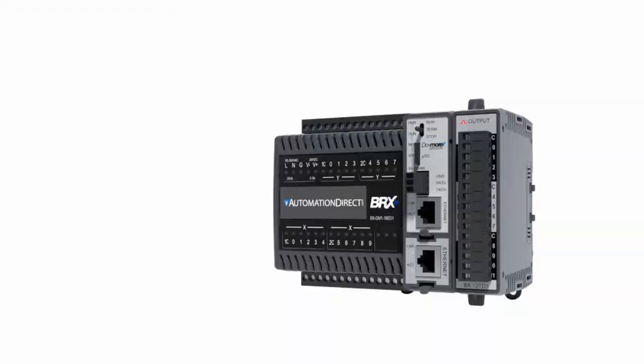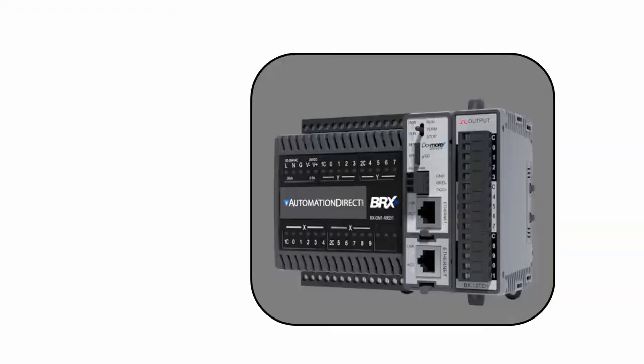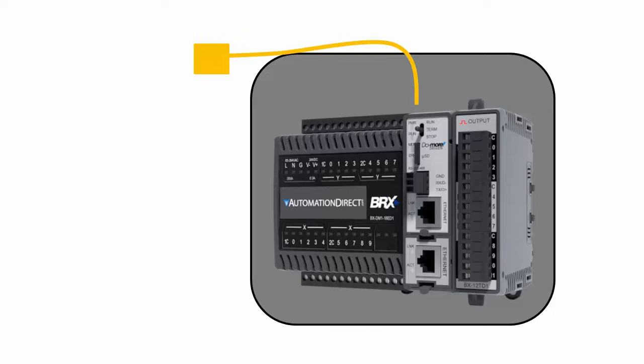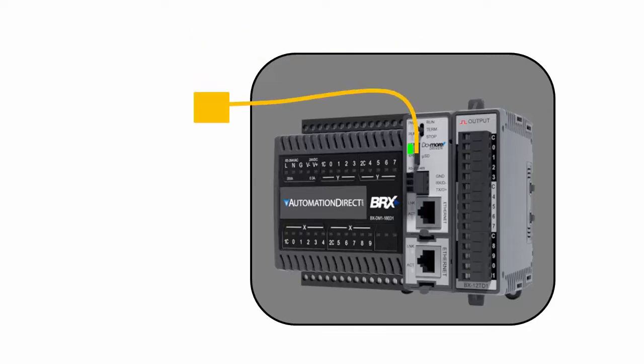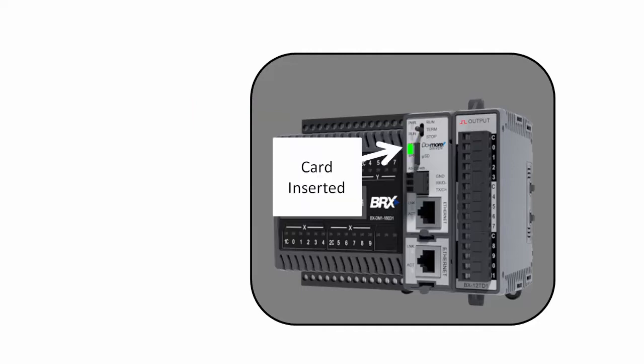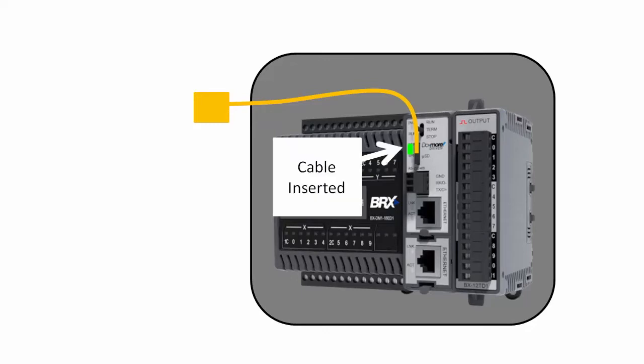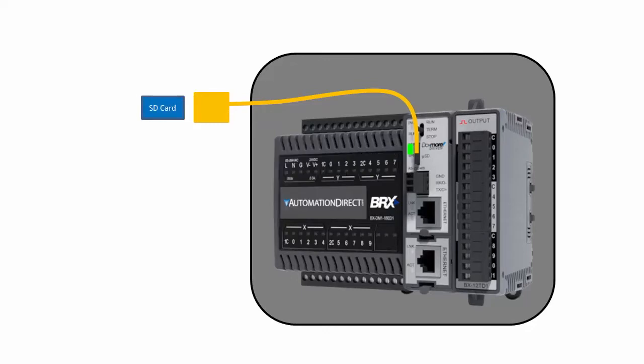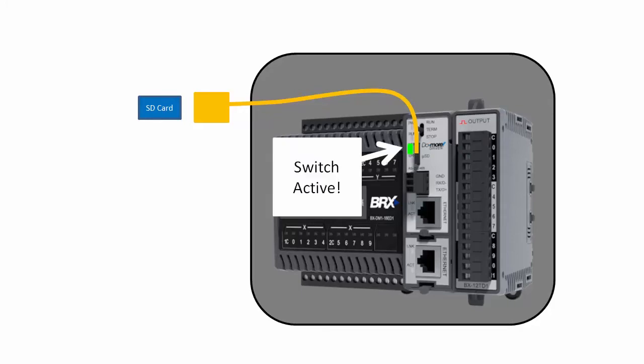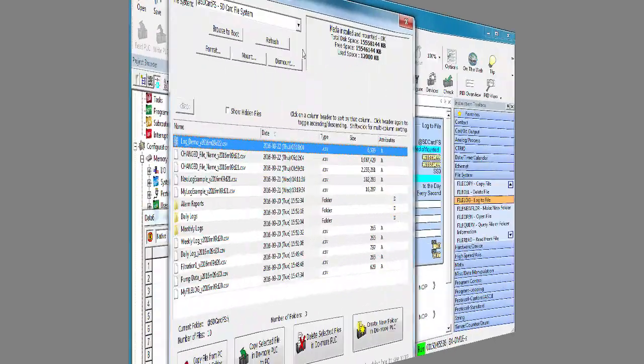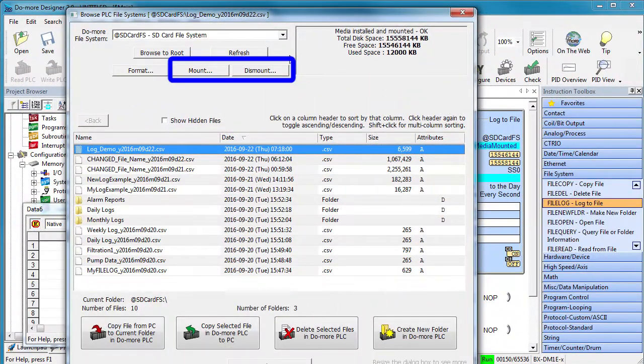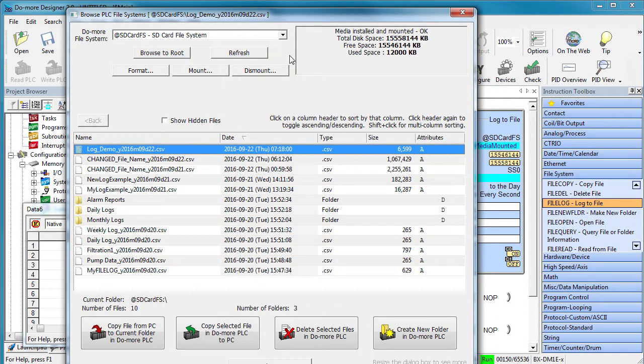Well, often times we'll build a system in an enclosure and we really don't want the end users opening the box for any reason, much less to extract a memory card. So what do we do? We add an extension cord so folks can access the memory card without opening the box. The problem with that is when you remove a card from the slot in the PLC, there's a mechanical switch that closes to tell the BRX PLC it's been removed. If you have an extension cable plugged in, the switch contact never happens and the BRX has no way of knowing the card was removed, which means the card is never cleanly dismounted and you run the risk of getting corrupt data on the card.